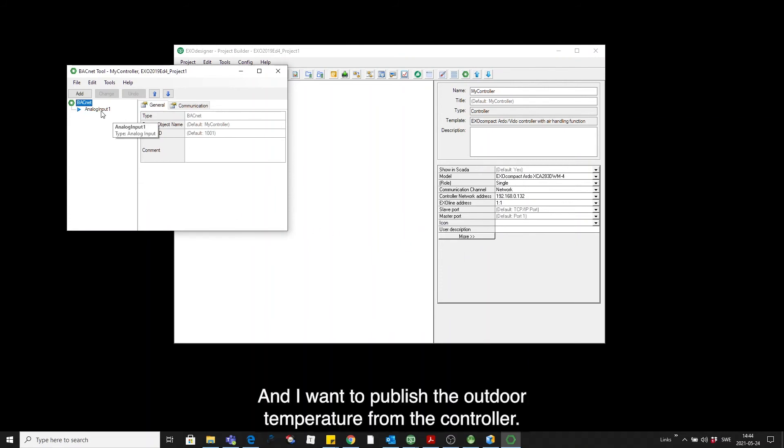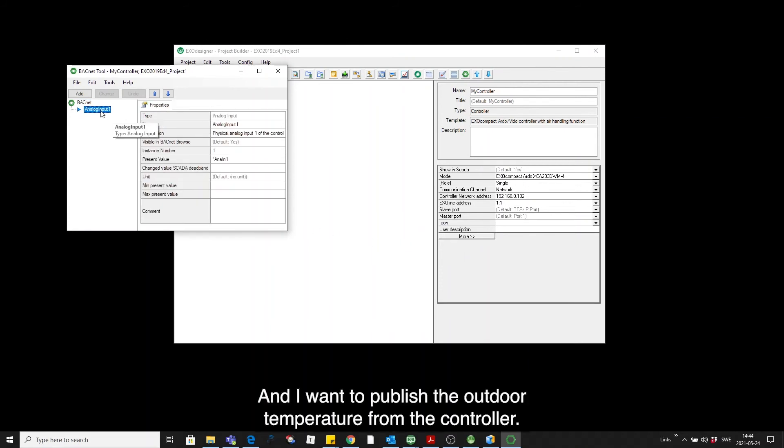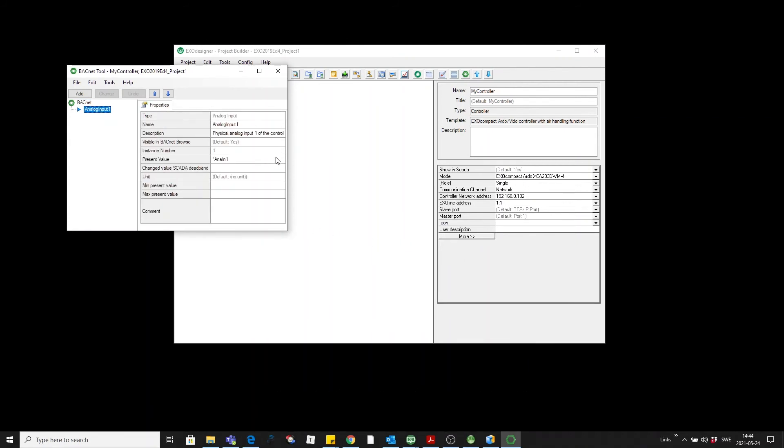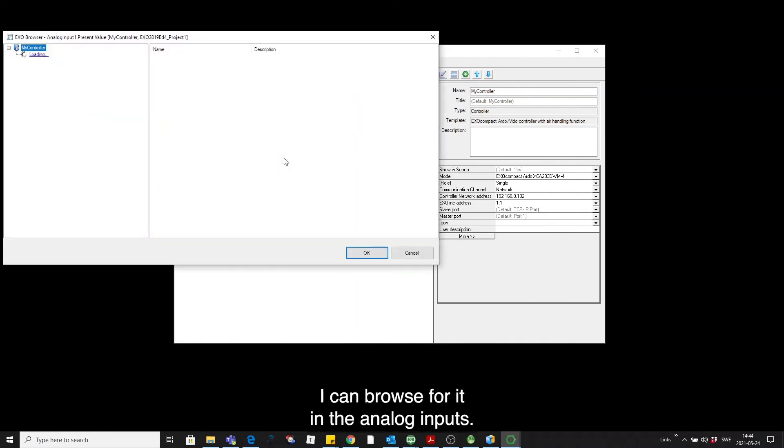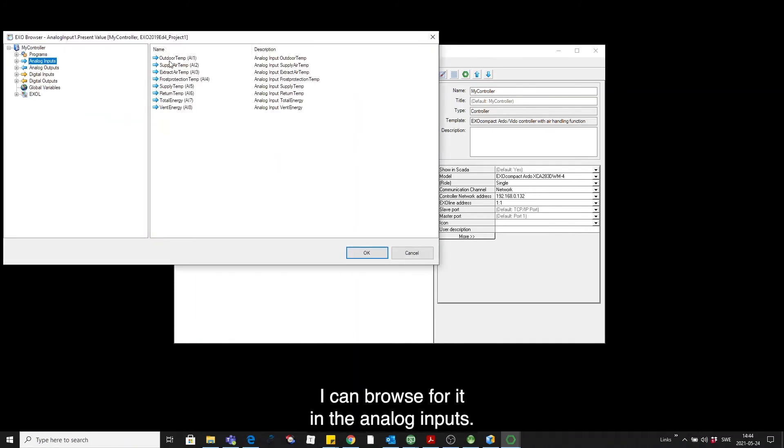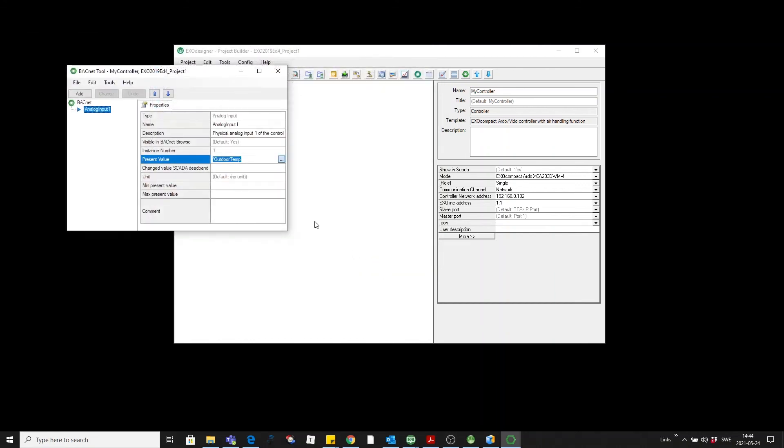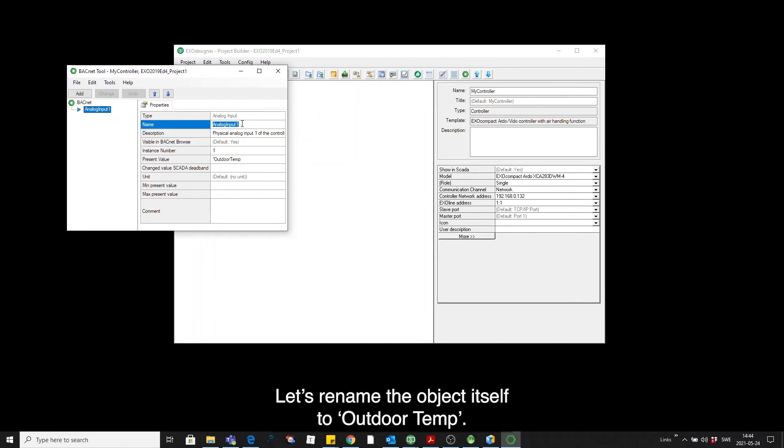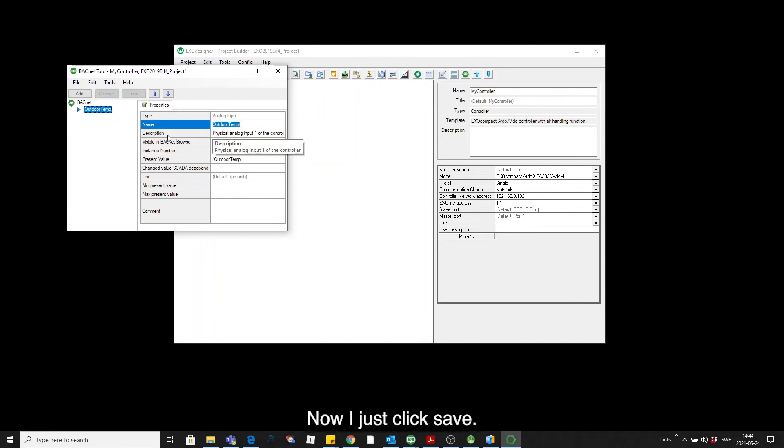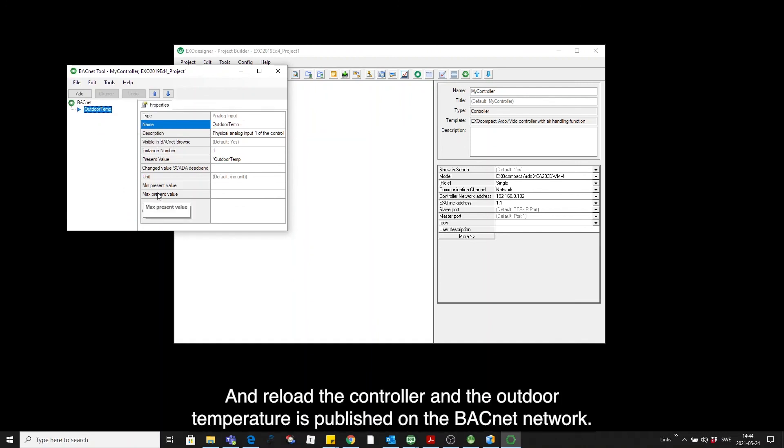And I want to publish the outdoor temperature from the controller. And I can browse for it in the analog inputs. Let's rename the object itself to outdoor temp. Now I simply have to save. And reload the controller and the outdoor temperature is published on the BACnet network.